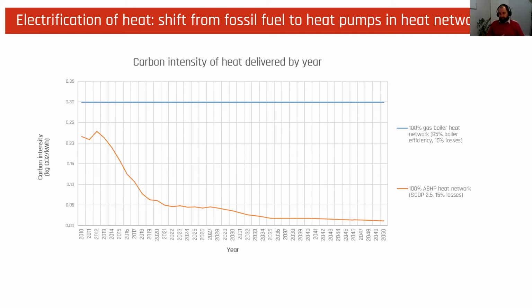This particular example just assumed an air source heat pump running at a seasonal COP of 2.5, which is actually very conservative, with the same heat network losses. And you can see already at 2020, the carbon emissions from an air source heat pump compared to a gas boiler is significant, and that's only going to drop as we get close to net zero by 2050.